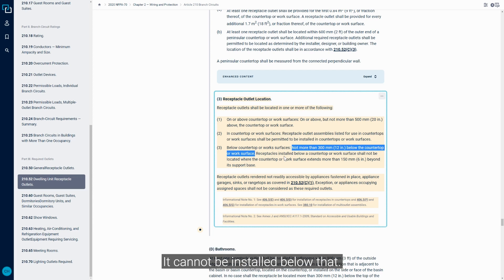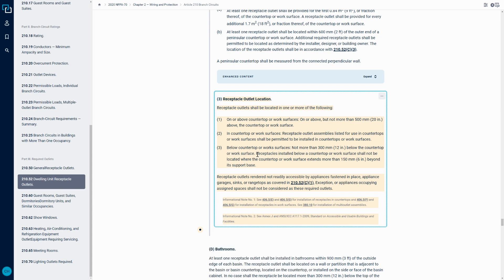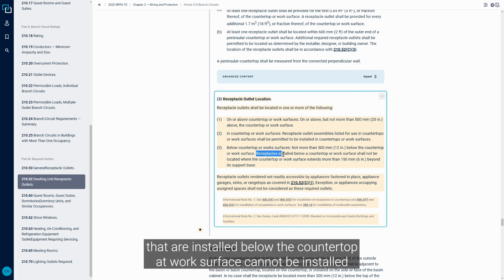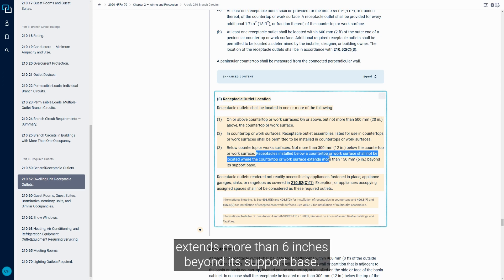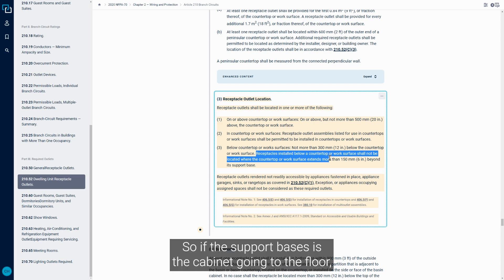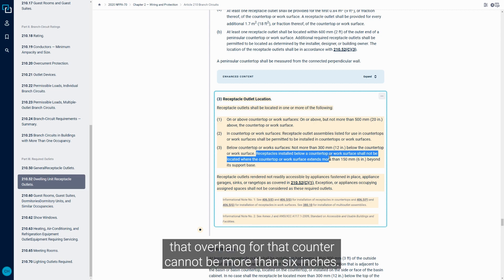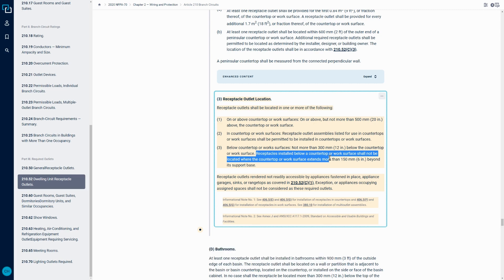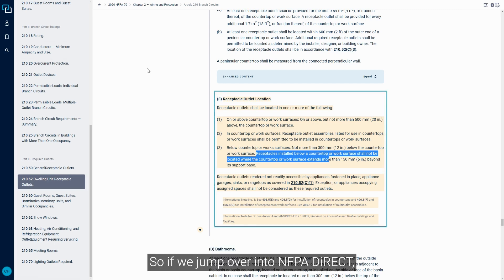The other part to that is that the receptacles that are installed below the countertop or work surface cannot be installed in a location where the countertop or work surface itself extends more than six inches beyond its support base. So if the support base is the cabinet going to the floor, that overhang for that counter cannot be more than six inches. If it is, you can't install that receptacle in that location.